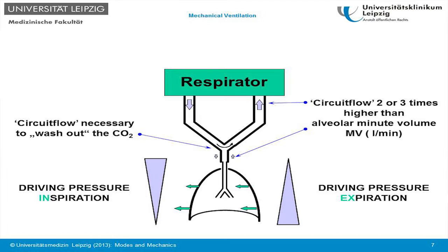From the respirator, we need a circuit flow going past the patient, which needs to be about 2 or 3 times higher than the alveolar minute ventilation, because the patient will also be breathing on its own and thereby draw from the gas flow that is offered by the ventilator. The inspiration happens when the pressure is higher here. Expiration is the opposite. When we lower the pressure in the circuit, the patient will exhale.